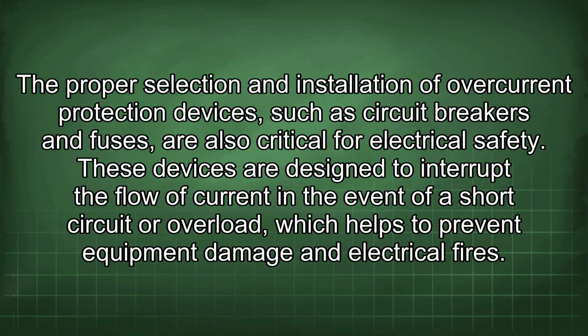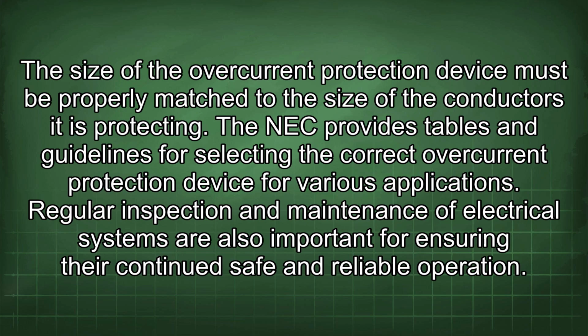The proper selection and installation of overcurrent protection devices, such as circuit breakers and fuses, are also critical for electrical safety. These devices are designed to interrupt the flow of current in the event of a short circuit or overload, which helps to prevent equipment damage and electrical fires. The size of the overcurrent protection device must be properly matched to the size of the conductors it is protecting. The NEC provides tables and guidelines for selecting the correct overcurrent protection device for various applications.